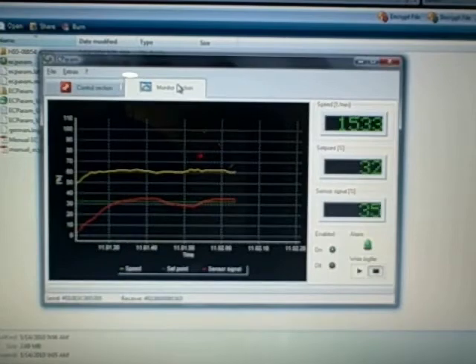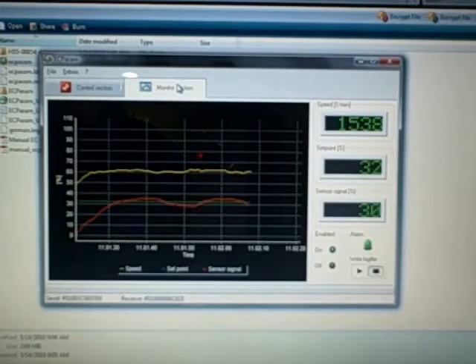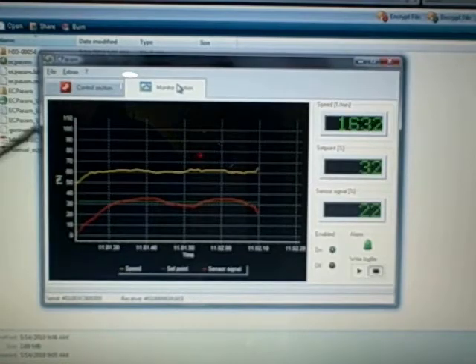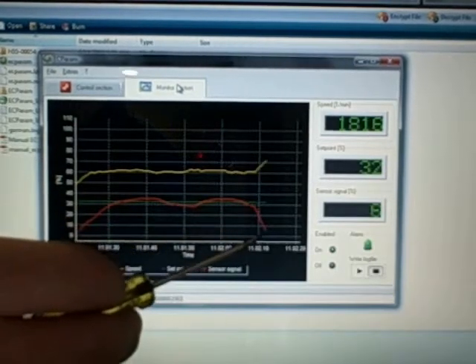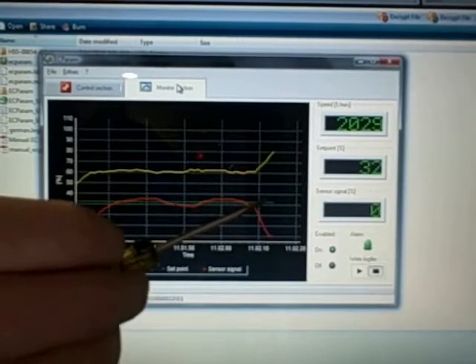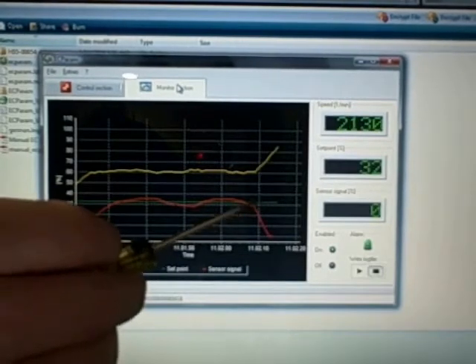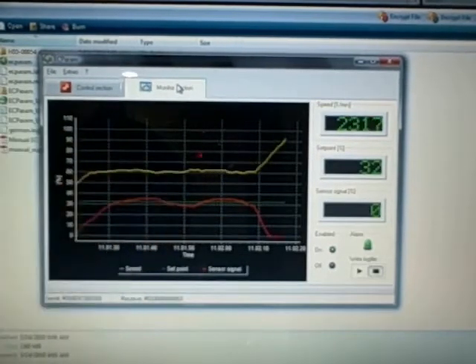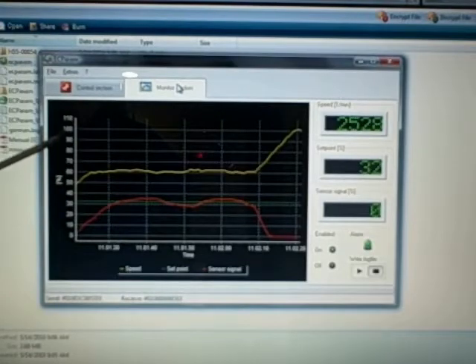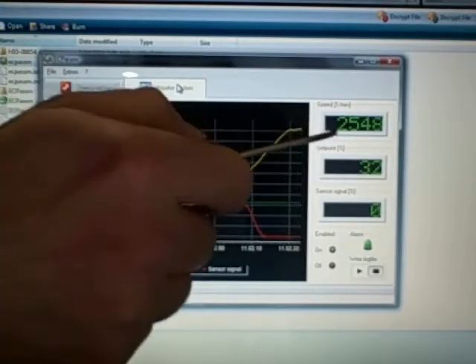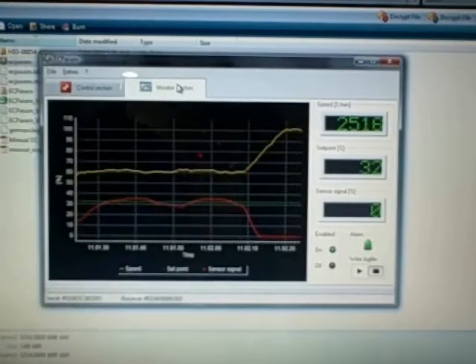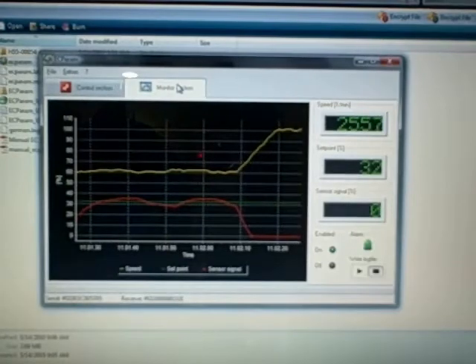So what we'll do is we're going to close the damper all the way. We'll shut the damper completely off so there's no airflow going into the motor. So you'll notice pressure drops, set point of the RPM stays the same. This is where we want it. So the fan's going to ramp up to compensate for the lack of airflow. It'll only run at 100%. Once it's run at 100%, 2550 or so RPMs, that's all it's going to do.